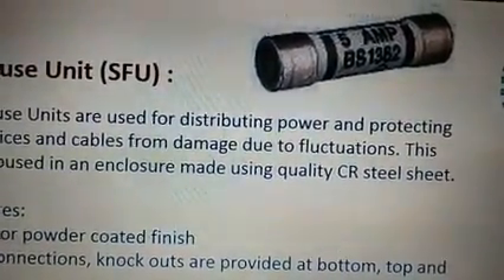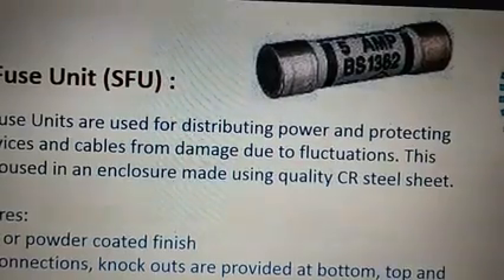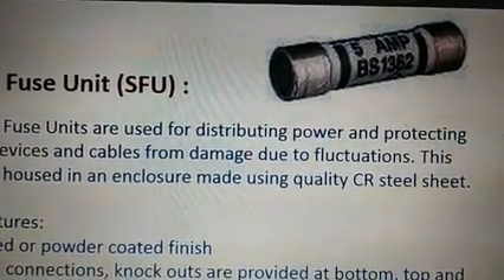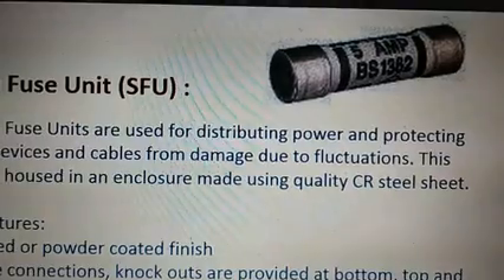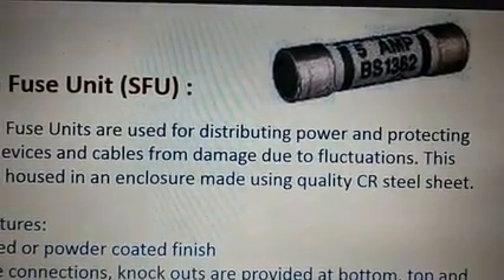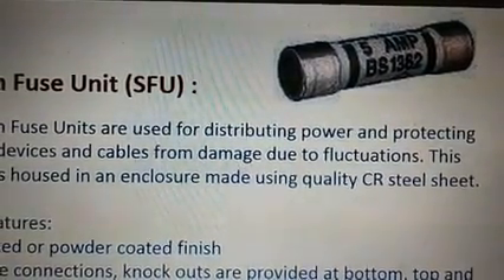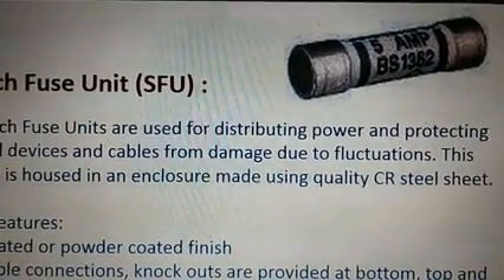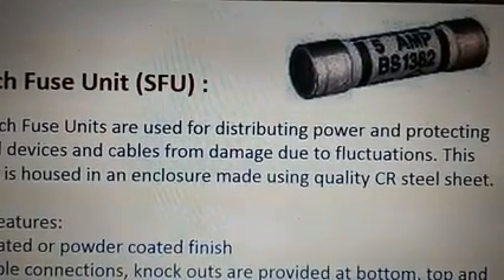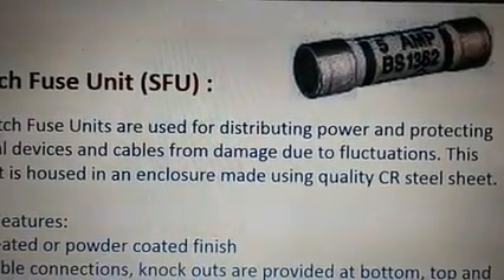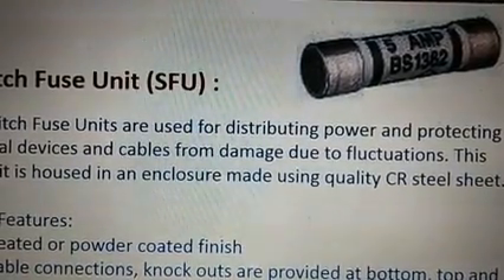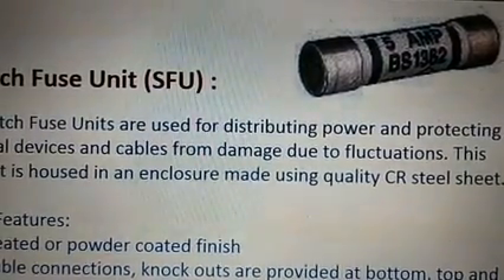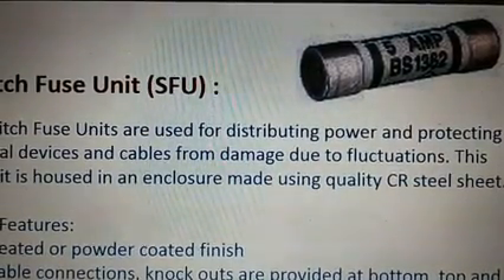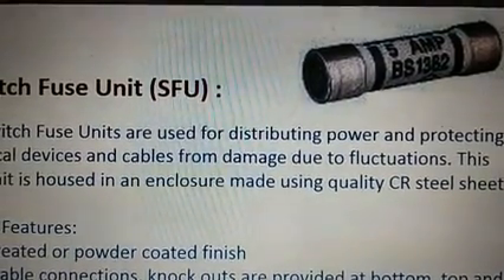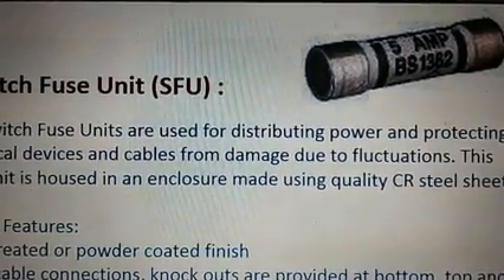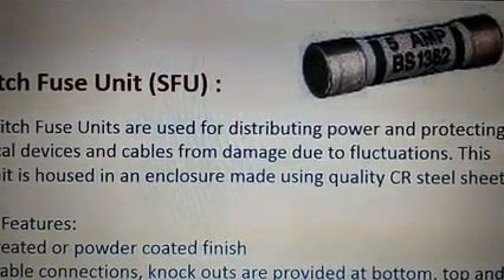It is an SFU rated as 5 ampere. The 5 ampere rating means it can withstand a maximum of 5 ampere current. You will see there are two ends, and these two ends are connected with a conductor internally, and that conductor can withstand up to 5 ampere. By any fluctuations or faulty conditions, if current exceeds 5 ampere momentarily or permanently, the wire or conductor within this fuse is going to melt and it will disconnect the supply, ensuring the safety of users as well as the equipment.